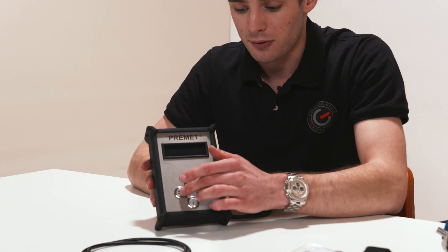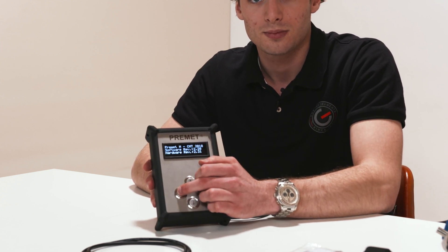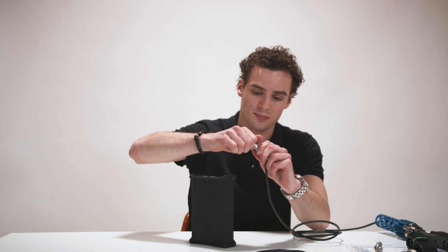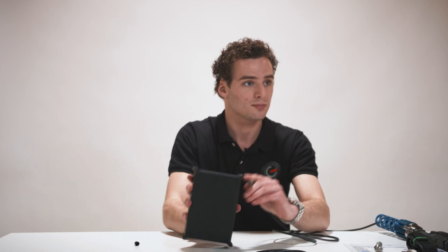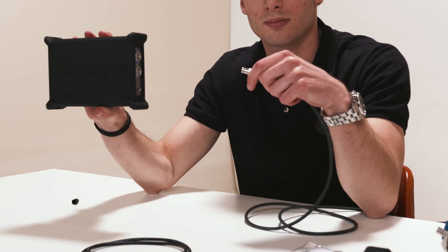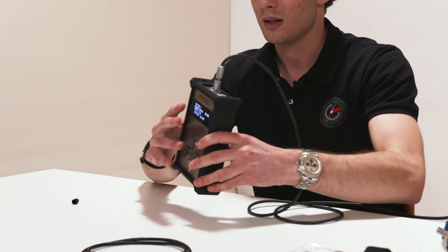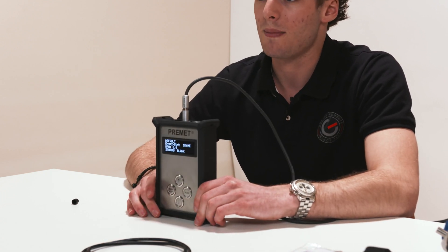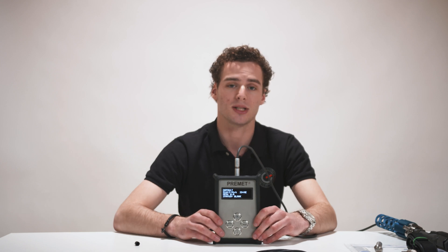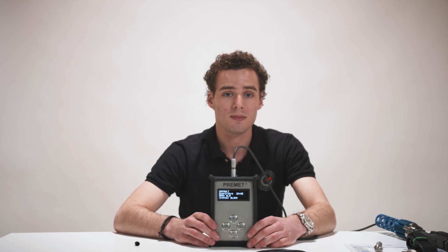So how do you use the PREMET? To start, press the on and off button for around three seconds. You can connect the pressure sensor by unplugging the rubber protection and plugging it into the PREMET. When finished, you can easily plug it out. You can now choose the engine you want to measure with the up and down buttons. Engines can be added with the PREMET software on a computer. Now adjust the scavenger pressure with the up and down buttons if needed, then push the measure button. Now you are ready to measure your cylinders without using the device again.